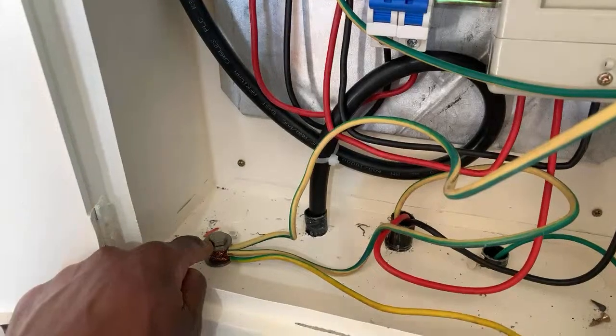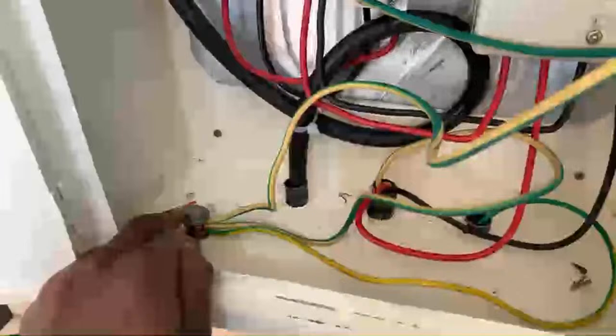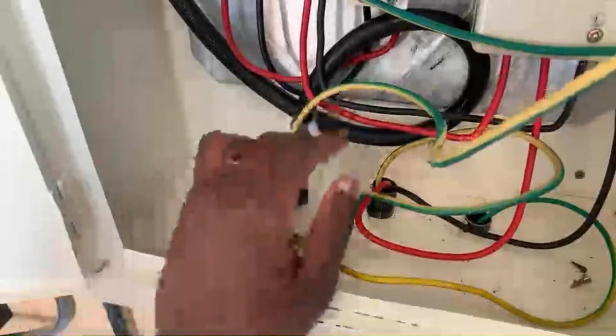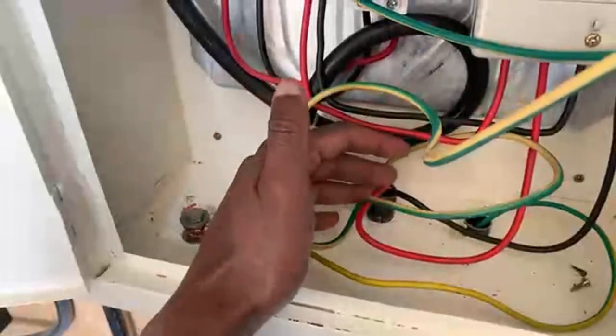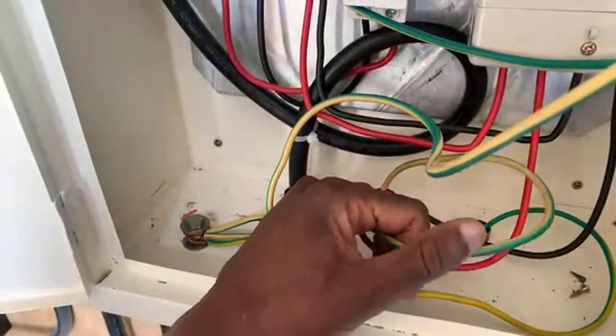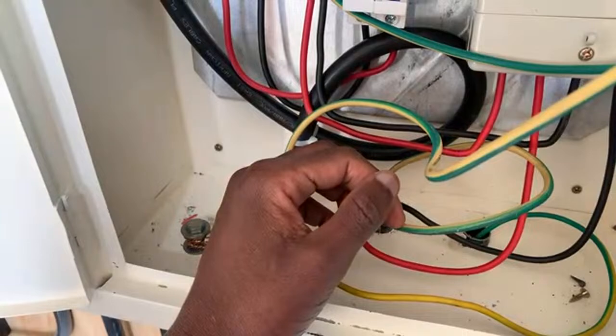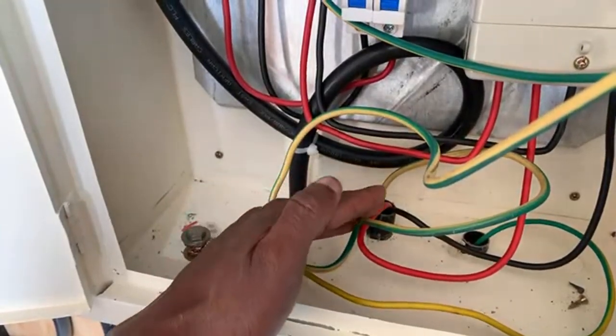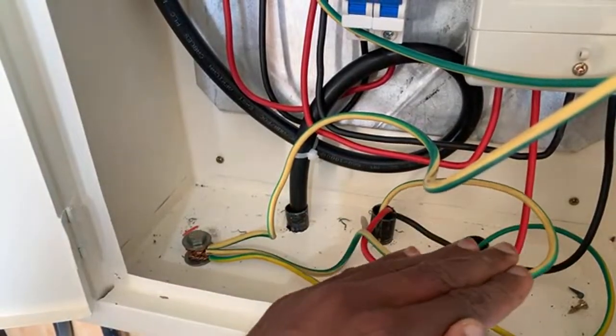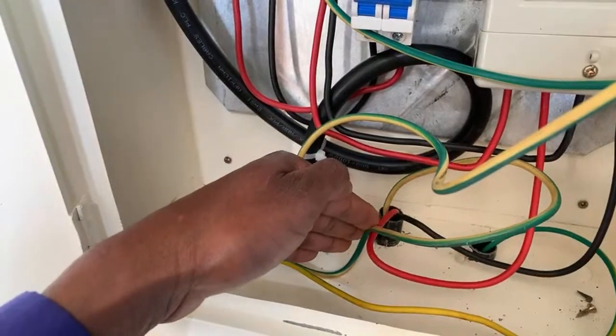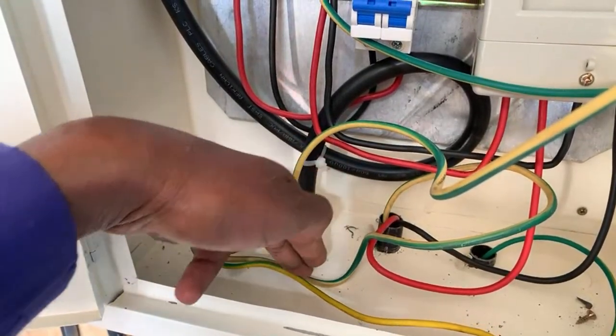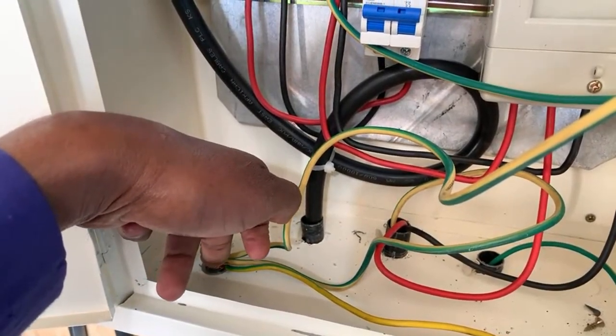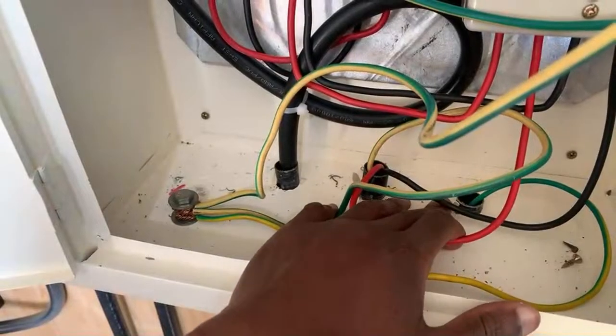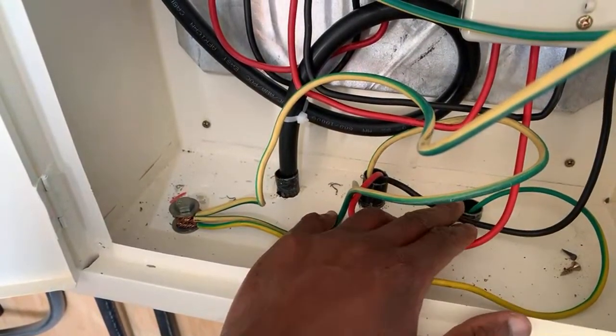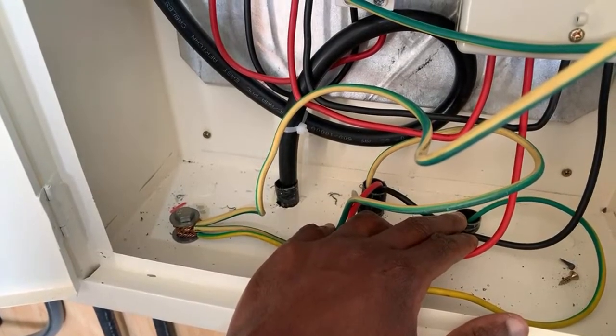Another thing we can ask: between this connection here, or between the earth rod connection all the way to the consumer unit or the electrical installation through this mains cable, is there a problem? From the house or the consumer unit, excessive charges travel through this earth connection cable, which of course has to be of the correct size, not less than 10, all the way to my connection here. Using this path, it will then flow very safely to the ground. At the ground, these charges will also find their way all the way to the source, the transformer.